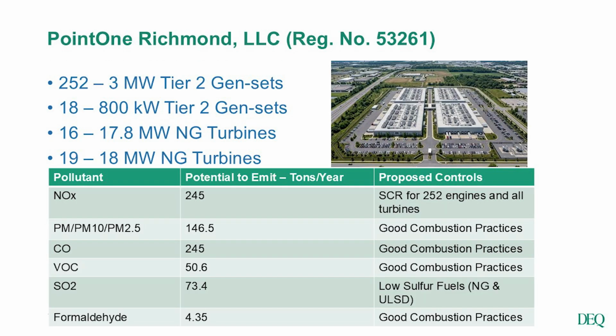The emissions units for the facility include 252 3-megawatt Tier 2 gensets, 18 800 kilowatt Tier 2 gensets, and approximately 35 18 megawatt natural gas turbines. The emissions, as you can see, are above major source thresholds, but still below prevention of significant deterioration thresholds.